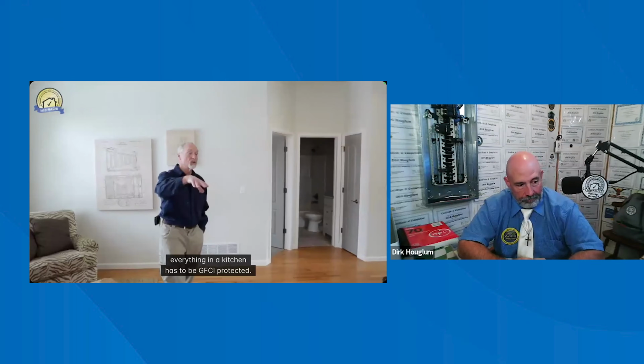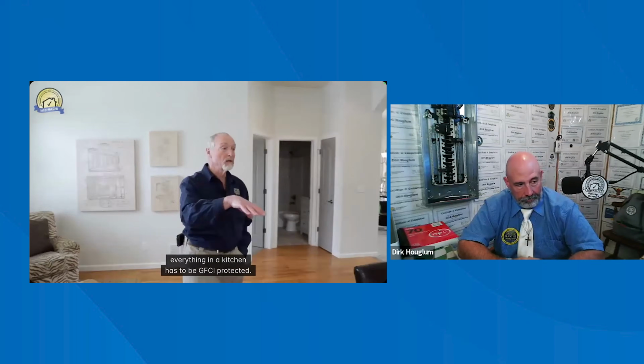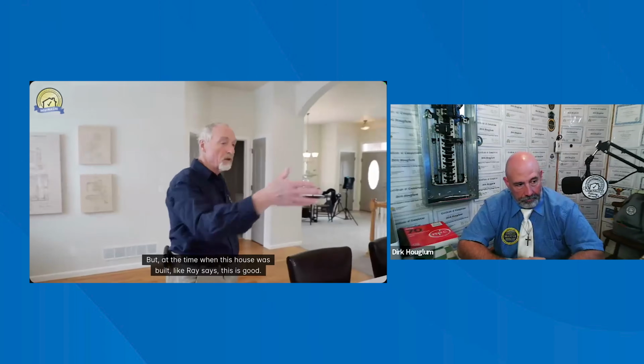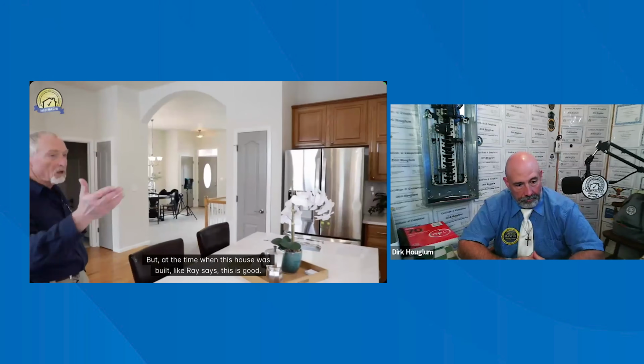When this house was built, the requirement for GFCIs was closer than 6 feet from the edge of the sink. So therefore, these actually are grandfathered in. We really don't have the authority to make this change or recommend this change. We can recommend it, but we can't enforce it. Today, everything in a kitchen has to be GFCI protected. But at the time when this house was built, like Ray says, this is good, we move on.